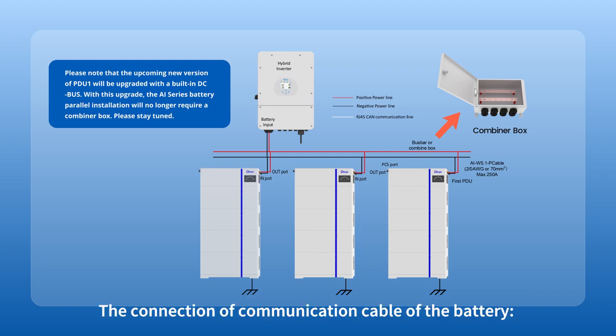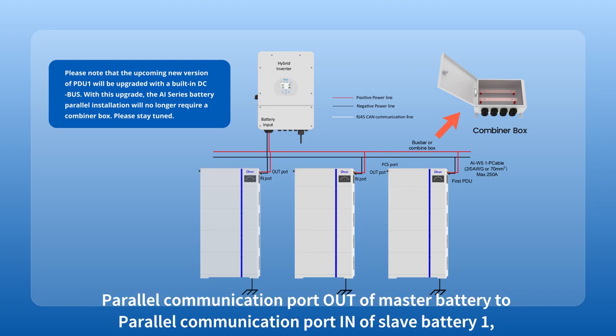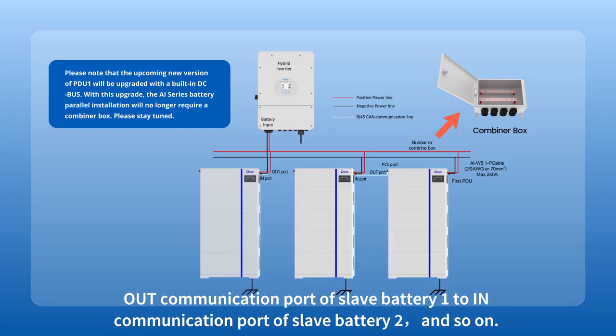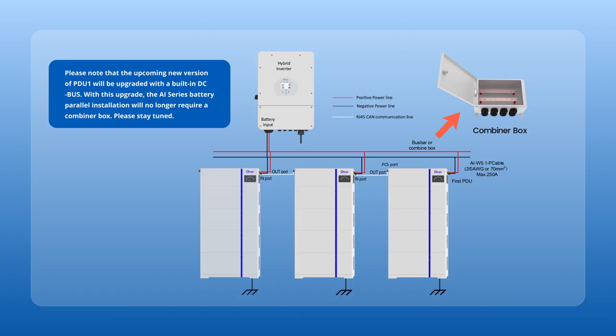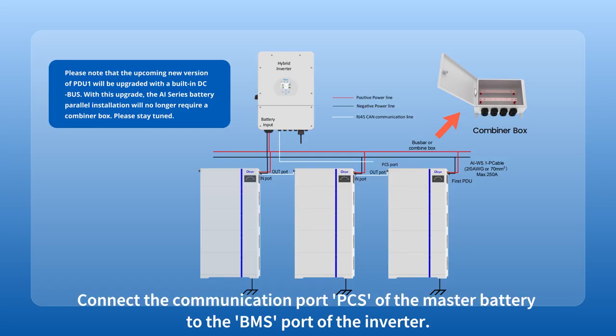The connection of communication cable of the battery: parallel communication port out of master battery to parallel communication port IN of slave battery 1, out communication port of slave battery 1 to IN communication port of slave battery 2, and so on. Connect the communication port PCS of the master battery to the BMS port of the inverter.